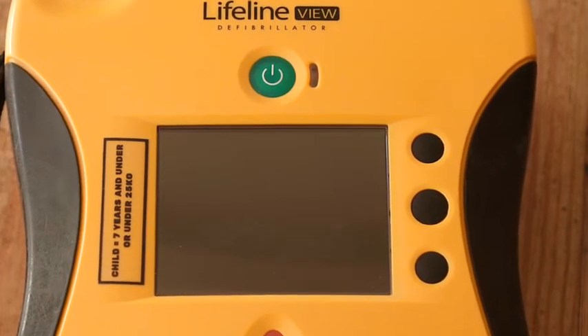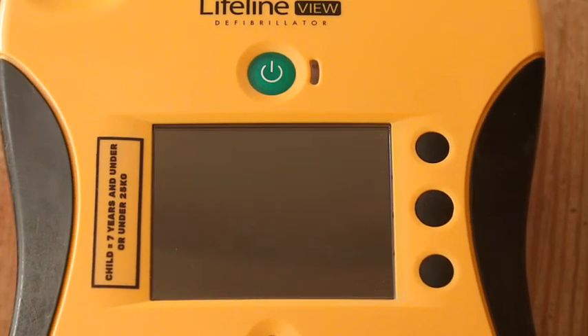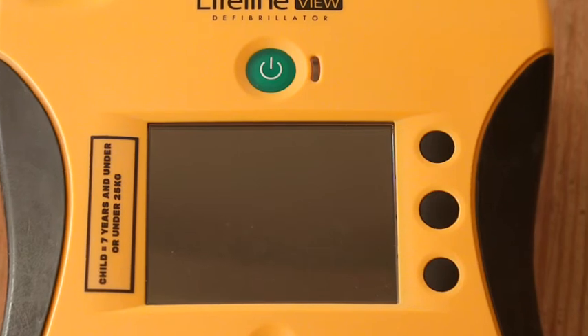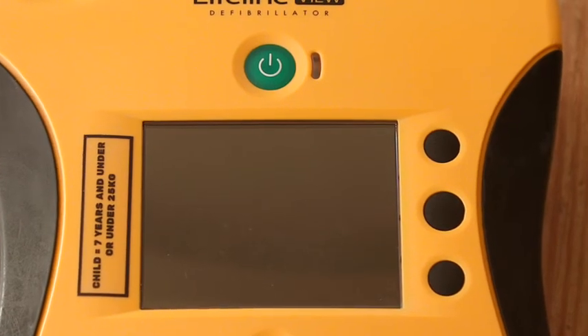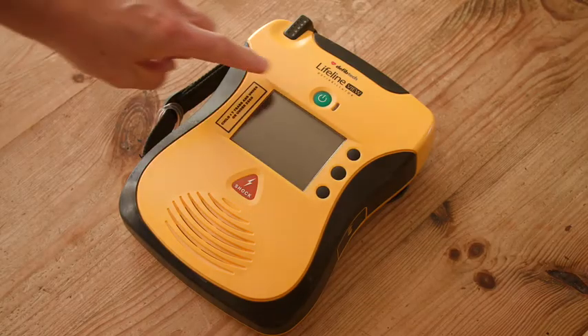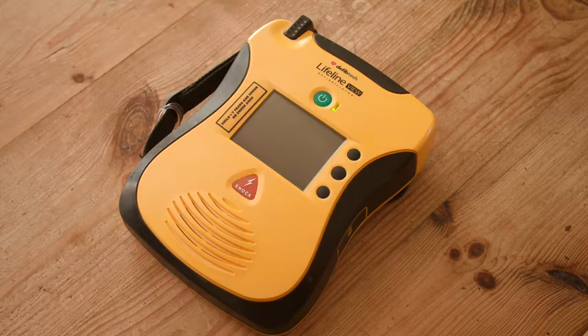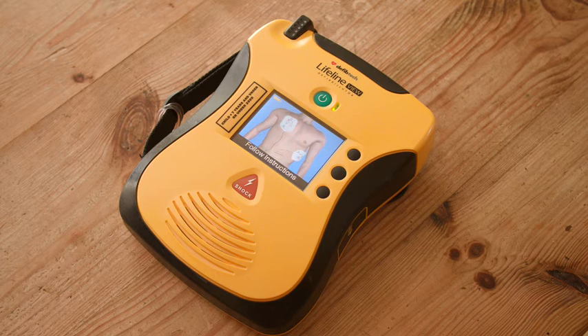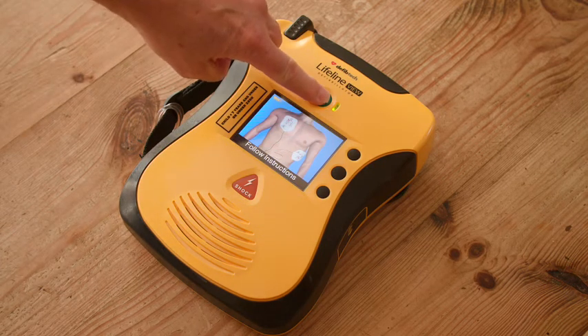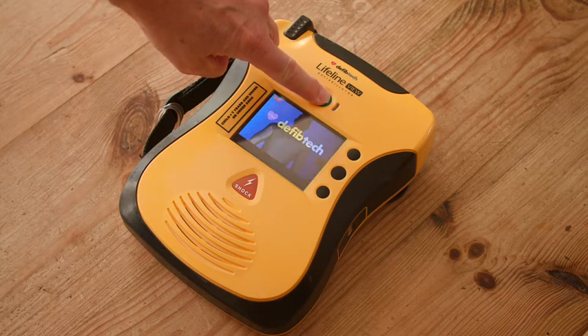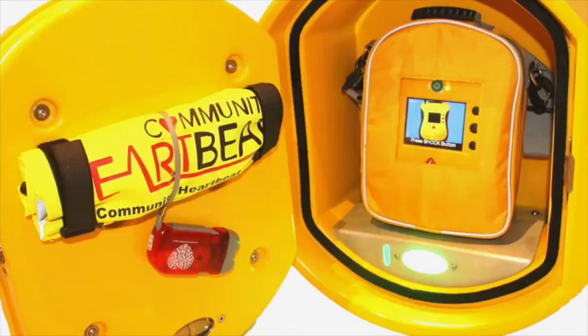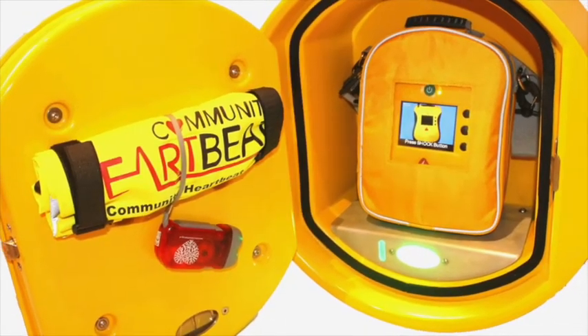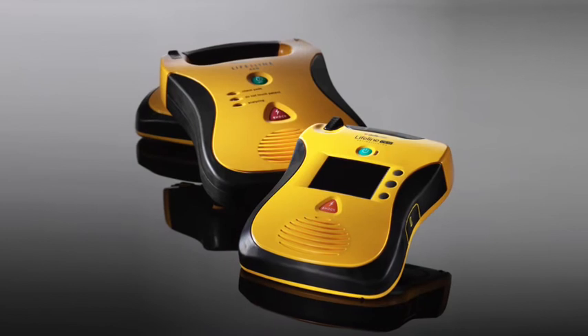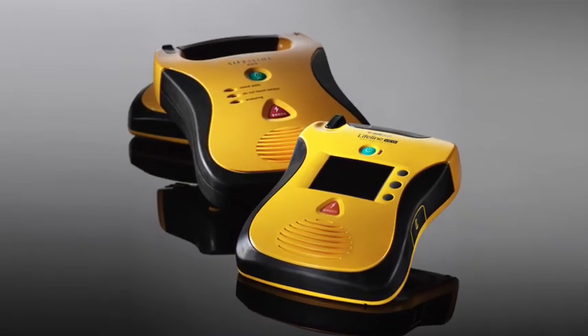You do not need to try to switch this off. There is no need to switch the defibrillator on to do checks. This just uses the battery up. If you do accidentally switch it on, then to switch off, press the green on/off button for 5 seconds before releasing. The defibrillator will switch off. It is really important regular checks are undertaken. If you need help, we are here to assist.